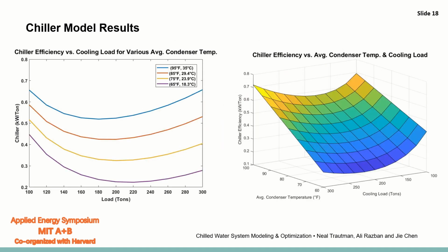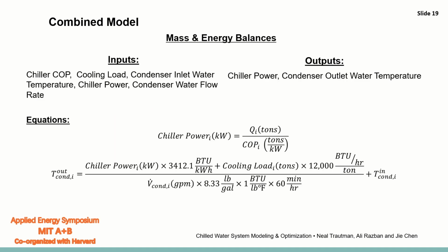Here are more relationships that we developed from the algorithm that we used, relating the chiller's efficiency to the cooling load using different inlet condenser water temperatures. The surface graph can be seen on the right, while certain line graphs for different outlet water temperatures can be seen on the left. Finally, that brings us to our mass and energy balance, which combines the model.